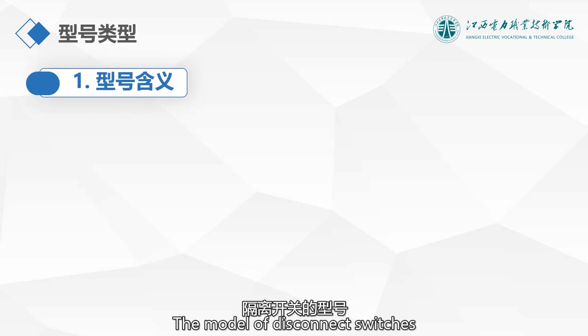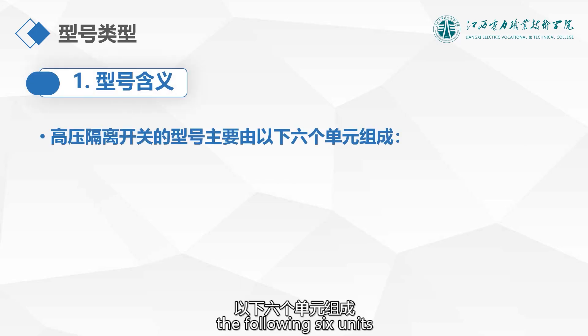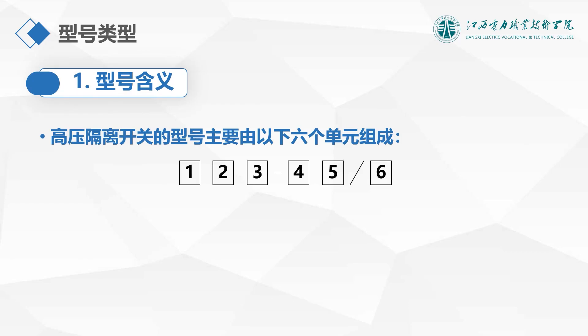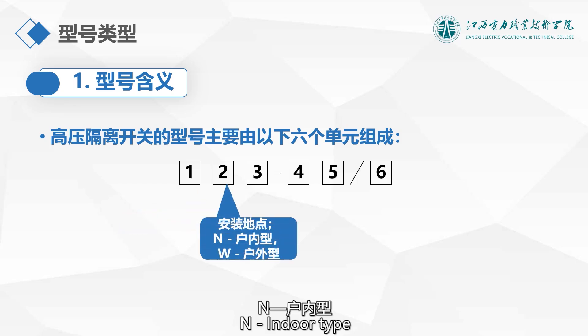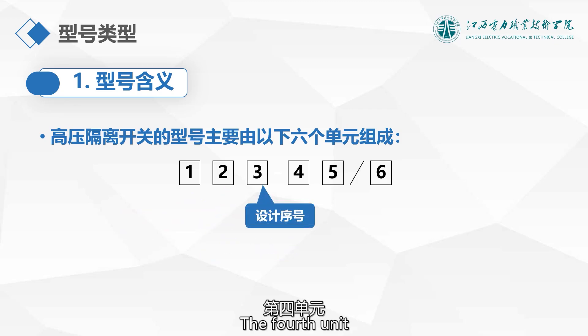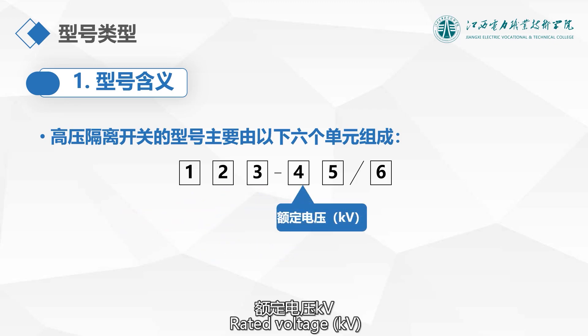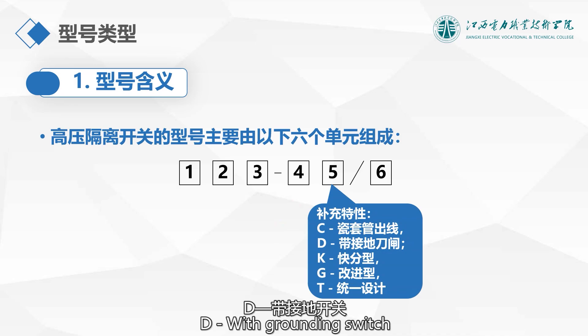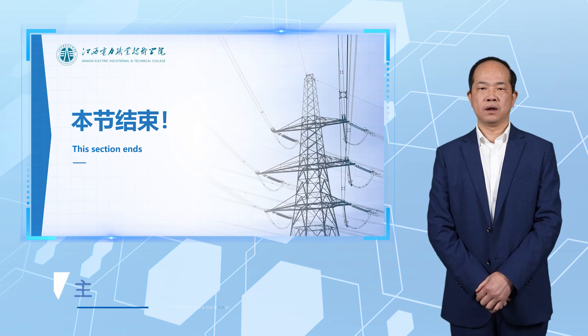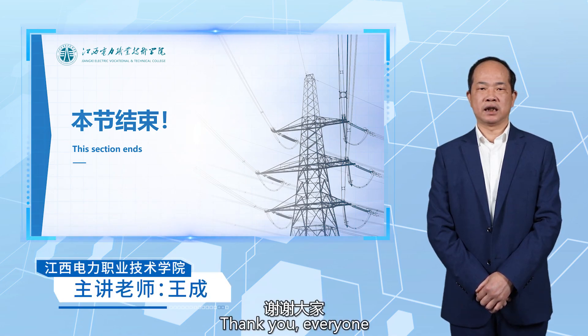The model of disconnect switches mainly consists of the following six units. The first unit is the product name: G for disconnect switch. The second unit is installation location: N for indoor type, W for outdoor type. The third unit is design sequence. The fourth unit is rated voltage in kV. The fifth unit is supplementary characteristics: C for porcelain bushing outlet, D for with grounding switch, K for quick break type, G for improved type, T for unified design. The sixth unit is rated current in A. This concludes today's lesson. Thank you everyone.